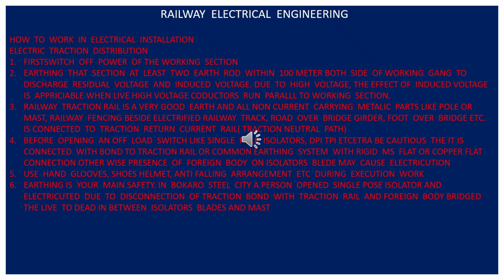Now, before opening an off-load switch, that means a single pole isolator: our single pole isolator is provided on the top of the mast with insulators. The isolator is on the insulator so that the mast and the isolator blade cannot be bridged. There must be insulation. Now, sometimes birds drop some foreign body on the blade of the isolators. So what happened? One of the staff went to open the isolator and he did not notice the connection from the mast to the traction rail, that is the bond. It is a low resistive path. If any mistake occurs, then the current will flow through the traction rail through this bond.